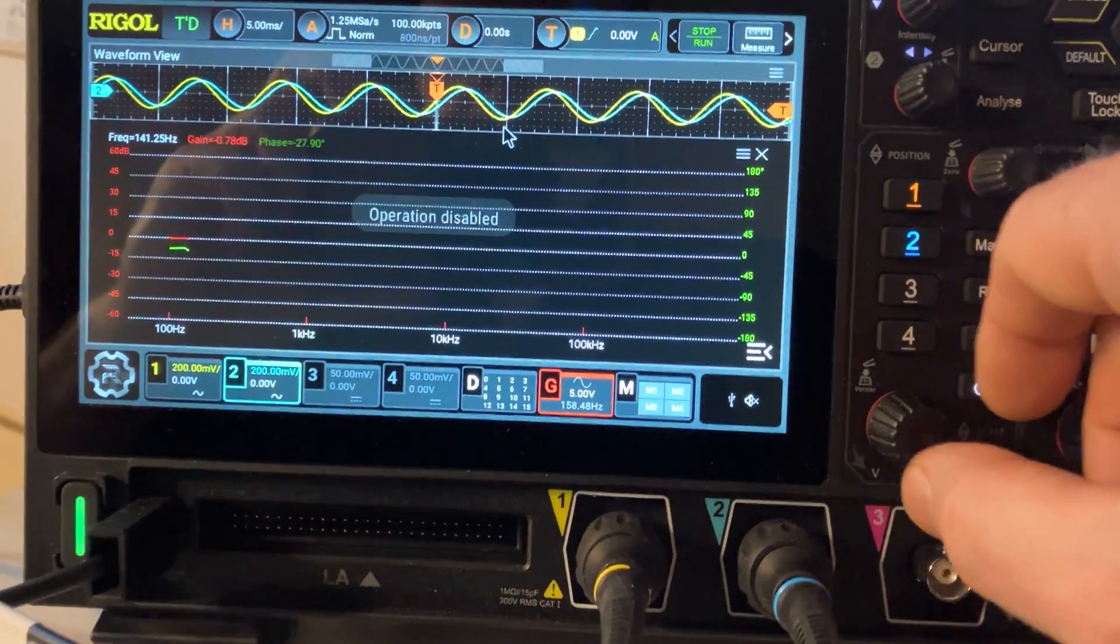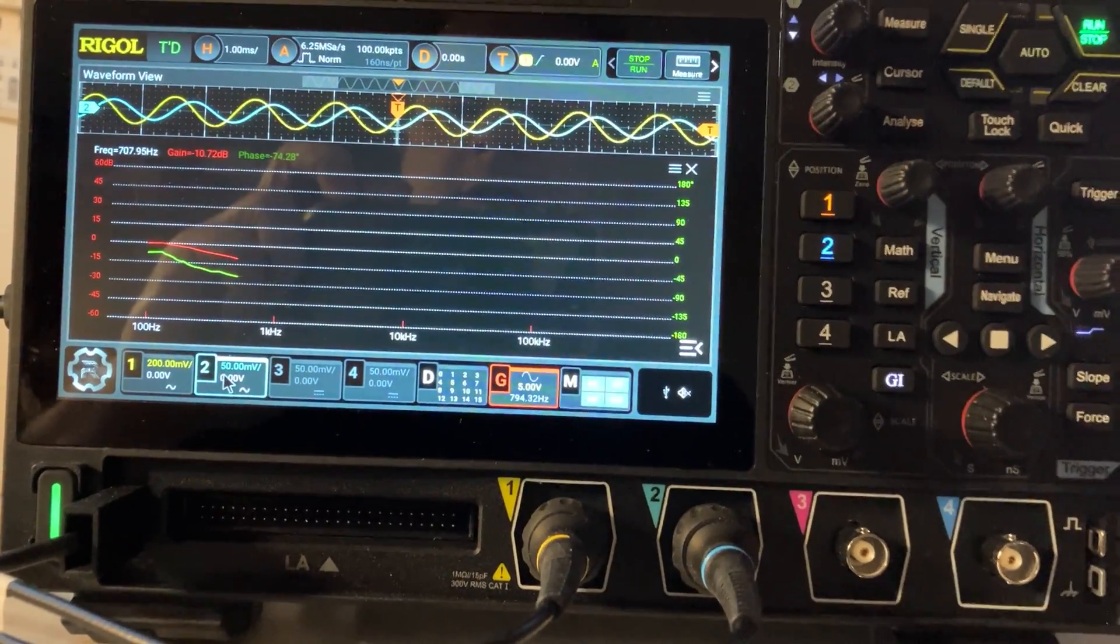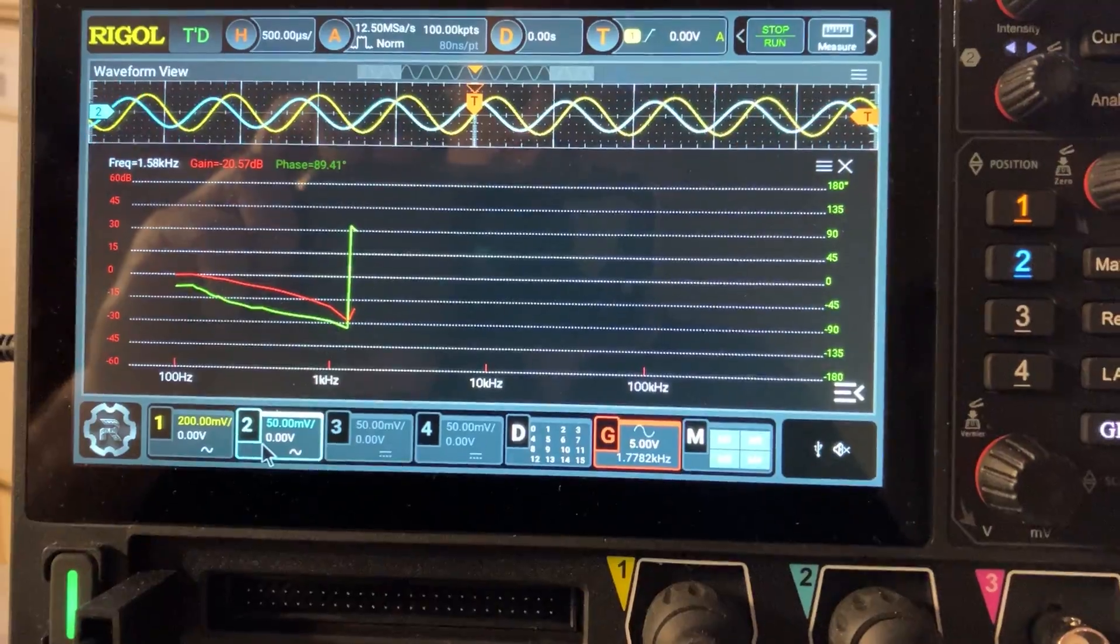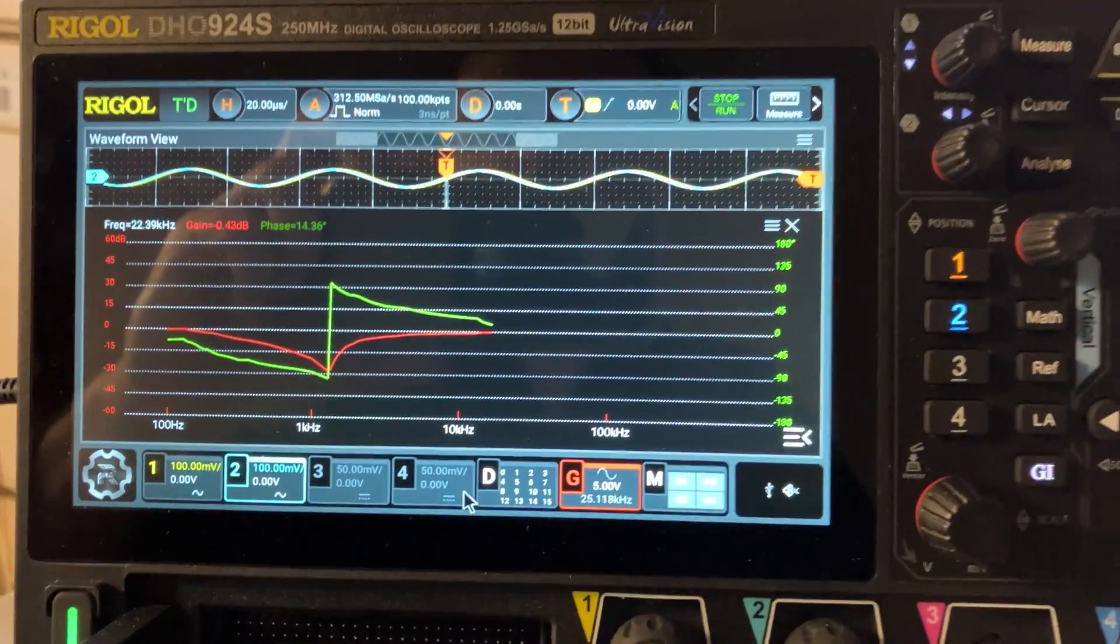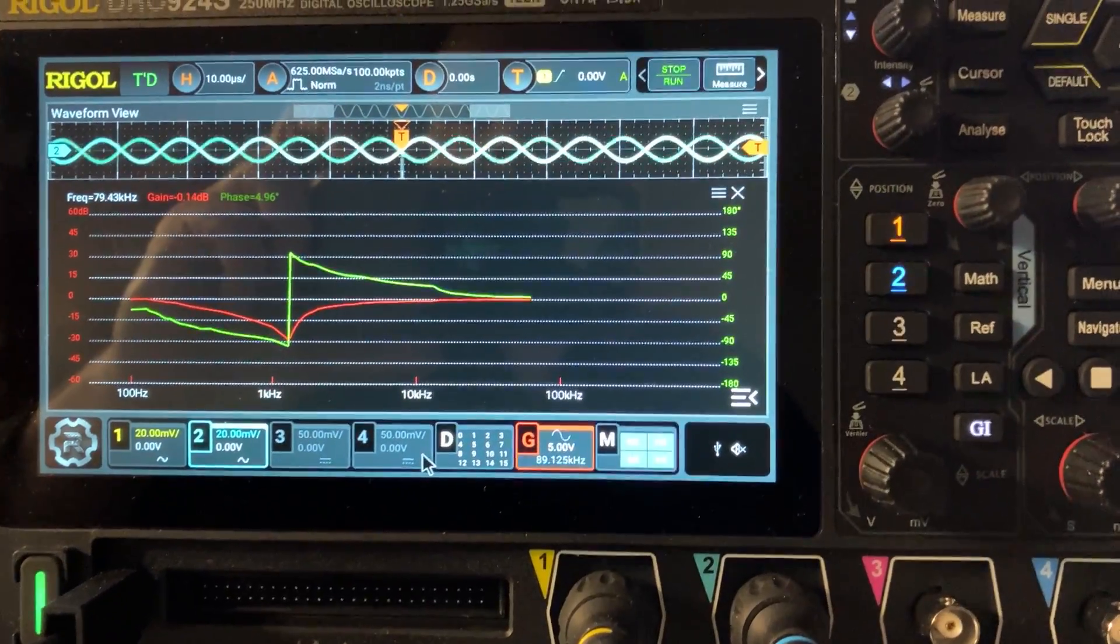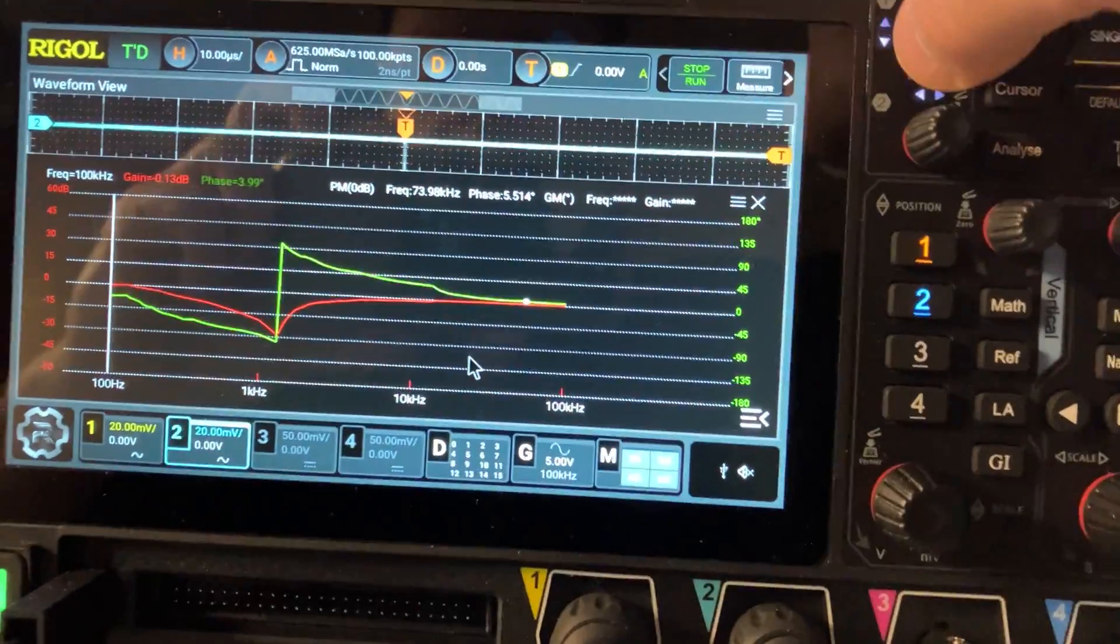While the thing is in acquisition, everything is disabled. This goes also for menus - they don't pop up. You could highlight something but you cannot change, because basically the scope is taking control of the amplitude, taking control of the frequency of the generator. Sometimes you could turn it off, but other than that, when the scope is completing its analysis, you don't have control.